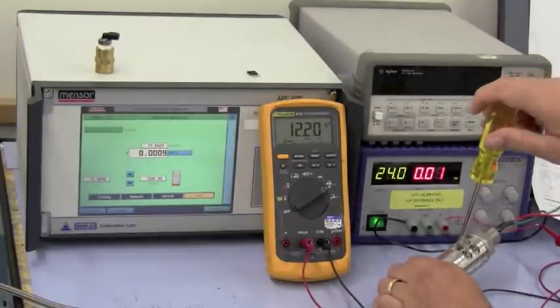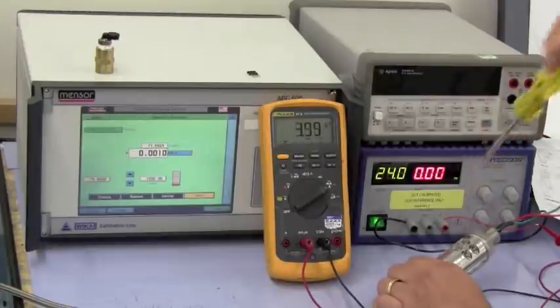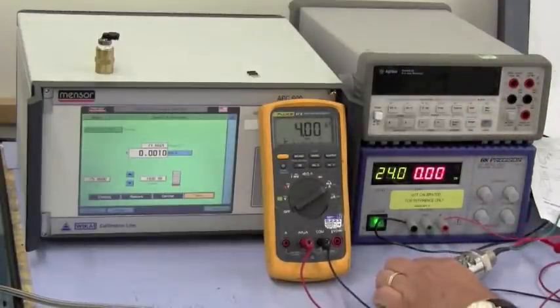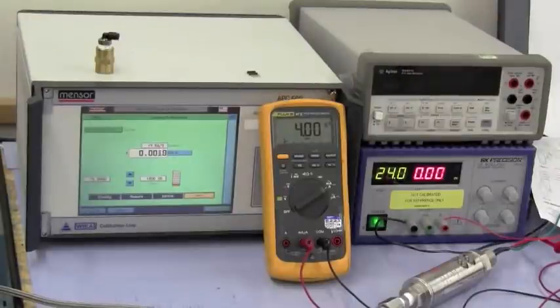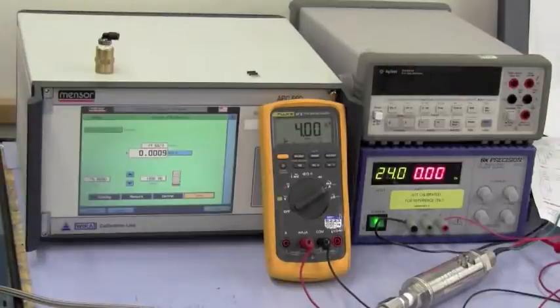I'll now close the CAL button. And you'll see that we've dropped down to 0, 4 milliamps. And you'll see that there's no interaction between 0 and span. I did not have to re-zero my transmitter.